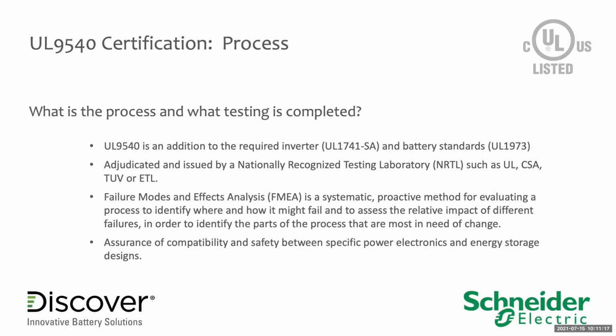But the UL9540 certification is over and above that, and it combines the operation of both devices together. It's adjudicated and issued through a neutral third party, a nationally recognized testing lab, or NRTL, such as UL, CSA, TUV, or ETL. They test to the UL9540 published standard.